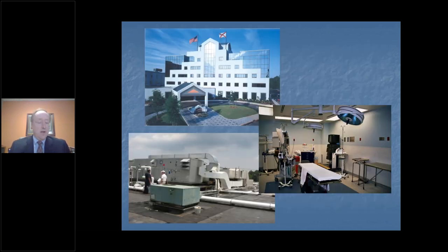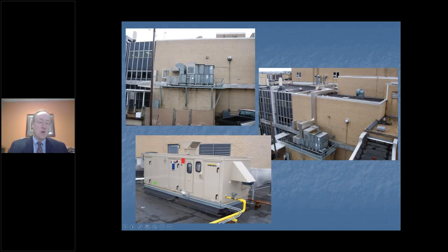Here's another hospital. We really did it the same way. That's a unit that's up on the roof that fed another air handler that served the surgical suite after it mixed this air with the return air. There's another hospital. This is the air handling unit that served through this duct work. It served the cardiovascular suite, and this was the outside air intake. So we removed that, what we call a gooseneck hood, and we then added this duct up to the roof and put the desiccant unit up there, and we were able to dry that air out, mix that with the return air, and then that goes through the duct work into the operating room.